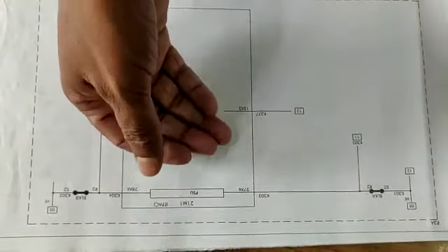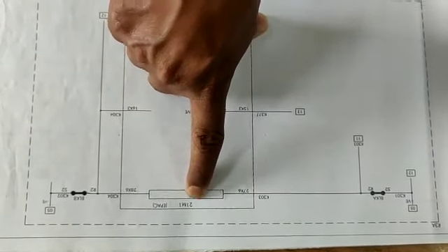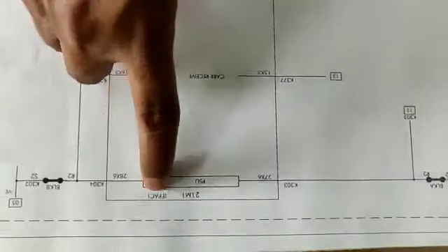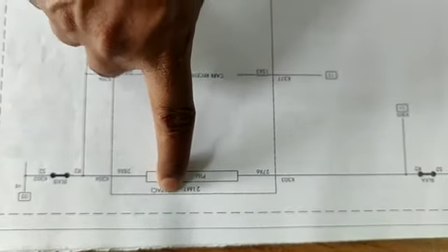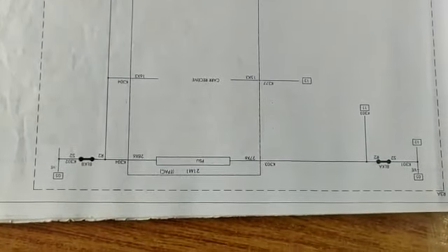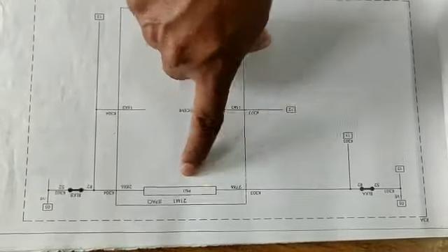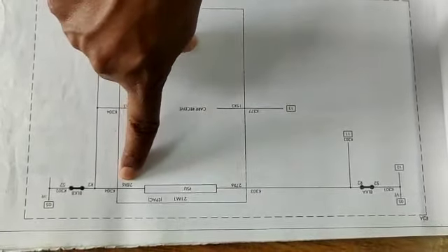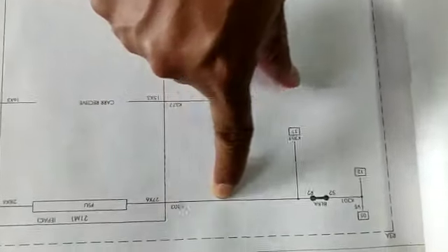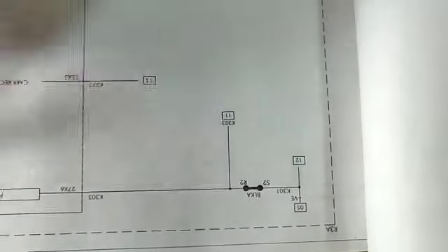If you look just one level above this PSU, you see there is 21 M1, and 21 is for distance protection and M1 is for main 1 protection, followed by some alphabets written inside a bracket, and this is basically the model number of the relay. That means this is main 1 distance protection, and the power supply unit of this relay is connected from, if you just trace this wire, one side written as positive, another side written as negative.